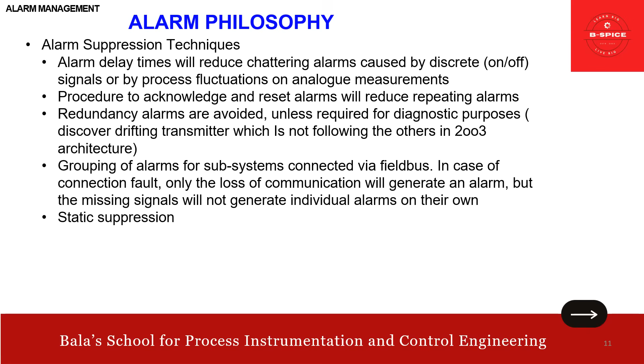Then again, another point. State-based alarming is only allowed if the process state can be determined automatically. What is that? Process state can be determined automatically. For example, we are disabling the low flow alarm when the pump is not running, like logical suppression, right? And in another case, real process values on analog transmitters are ignored when they are in simulation mode, right? Yes. So these are the things we can actually go for. State-based alarming.